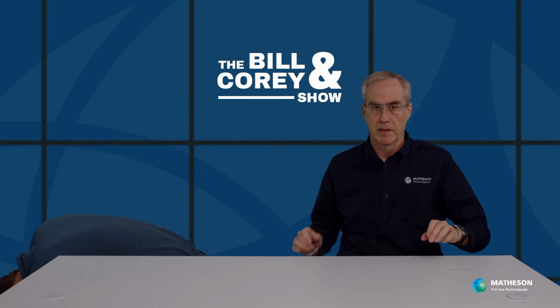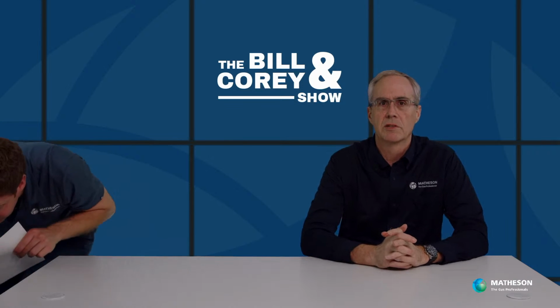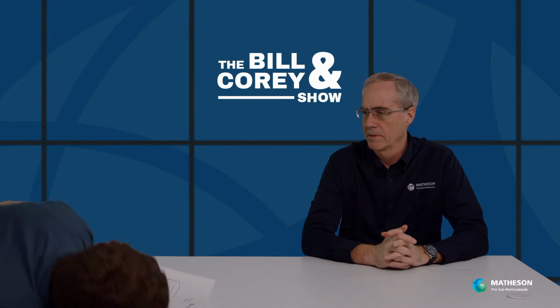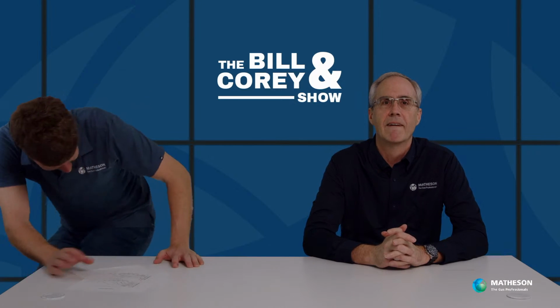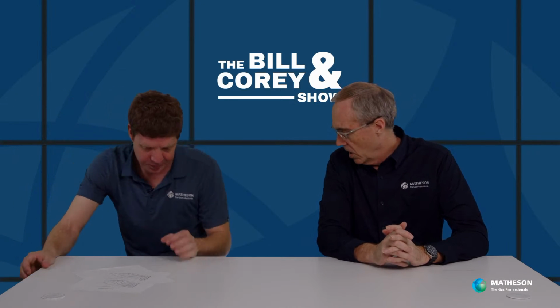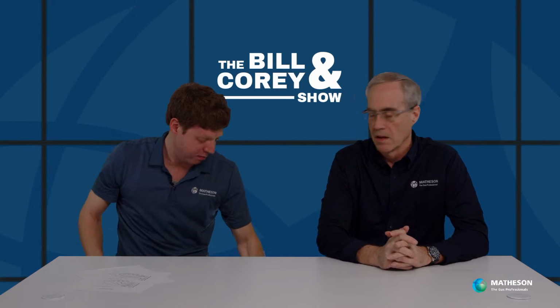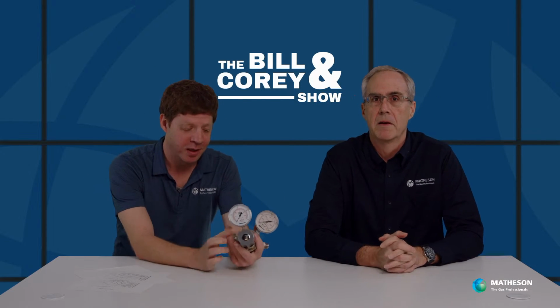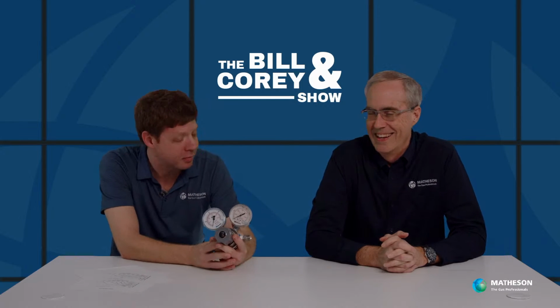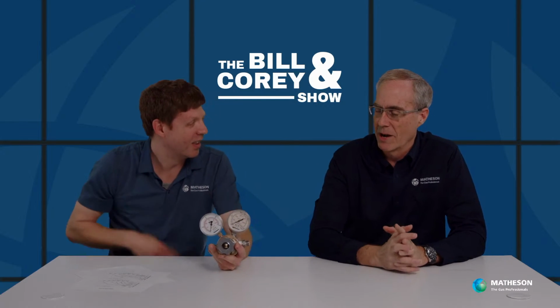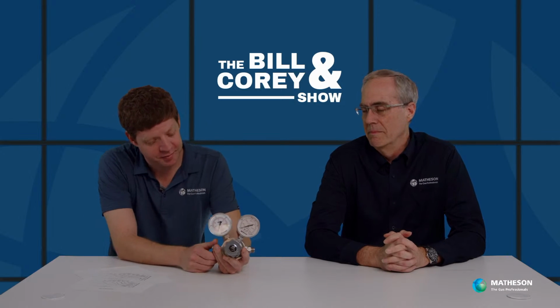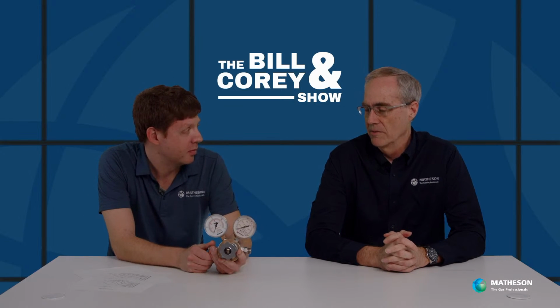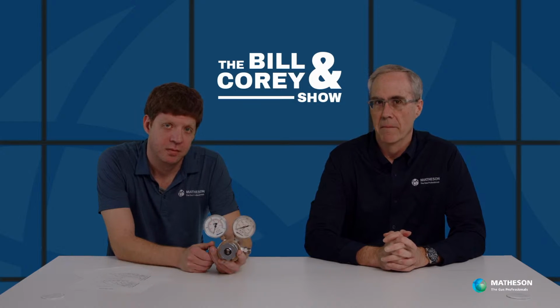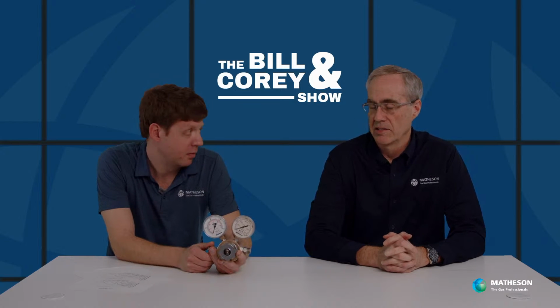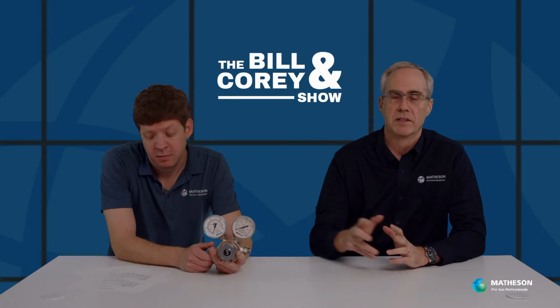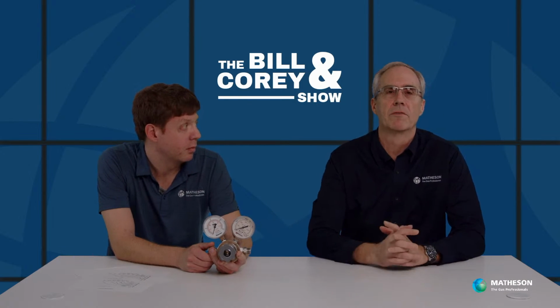Okay. Next question. Someone has a regulator, which is the 3200 series inline, and he returns it. It's a different problem on here. They're having flow rates of typically 4 to 8 CFM, and they had occasional excursions to 12 CFM, and they're using the model 3203, which is appropriate for this.